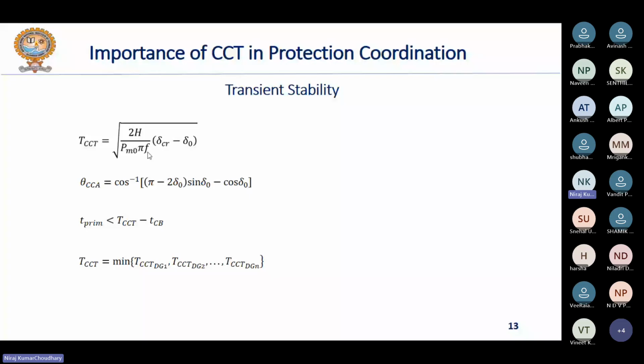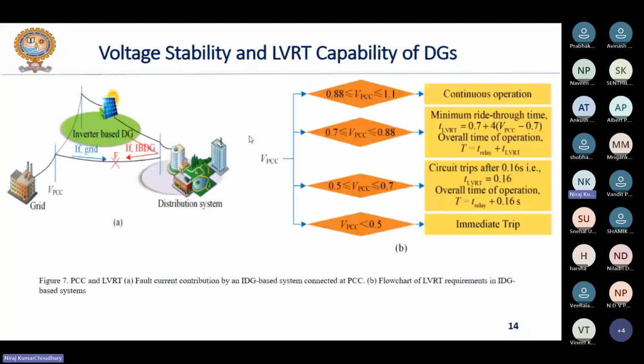Now, another aspect is the voltage stability and low voltage ride through capability of your DGs connected to the system. It is also one of the crucial challenges faced by the power system operators, that is the utility side.